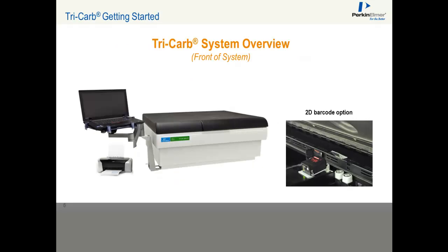Communications to the Tricarb will be via an external laptop computer, which is provided and not an option, communicating through a USB port to the instrument. The system is controlled by an external laptop with a Windows 7 operating system. The laptop includes a CD/DVD writer, Ethernet connection, and 3 USB ports.